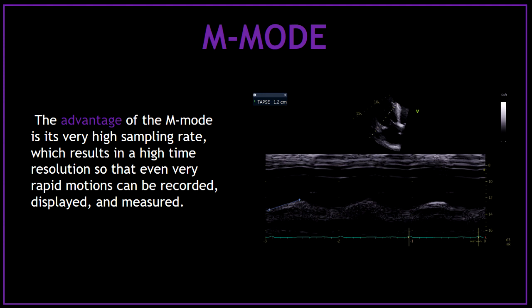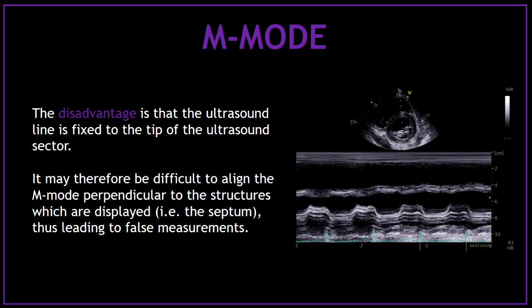The advantage of the M-mode is its very high sampling rate, which results in a high time resolution so that even very rapid motion can be recorded, displayed, and measured. The disadvantage of the M-mode is that the ultrasound line is fixed to the tip of the ultrasound sector. It might, therefore, be difficult to align the M-mode perpendicular to the structures which are displayed, leading to false measurements.